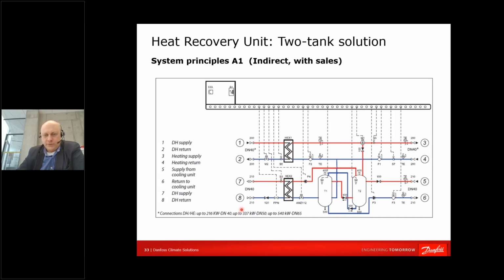Application with two tank solution and with possibility of sale of energy. So we have an extra appendix here. When we are over with the charging of the tanks, so tanks are charged, the building says I don't want energy, so we can start gradually pump P4. Also, we should install here an additional pump with a frequency converter, and we are gradually starting force pumps to increase pressure. And when we are overcoming pressure in the supply line somewhere here, we're connecting these pipes, and we can gradually start selling or delivering energy to the district heating utility, as long as we have energy here, of course.